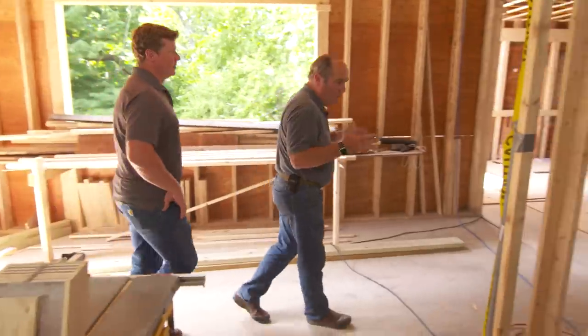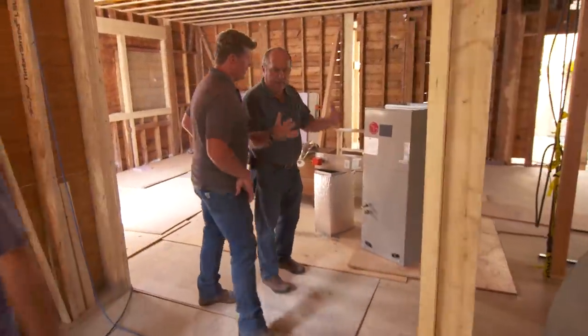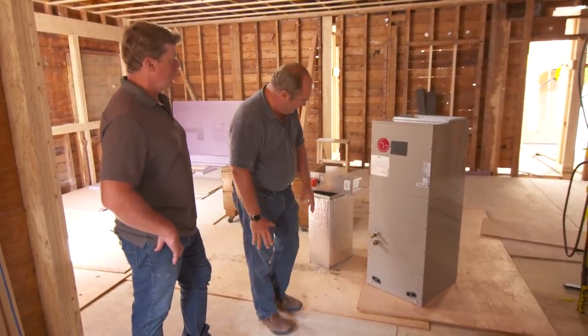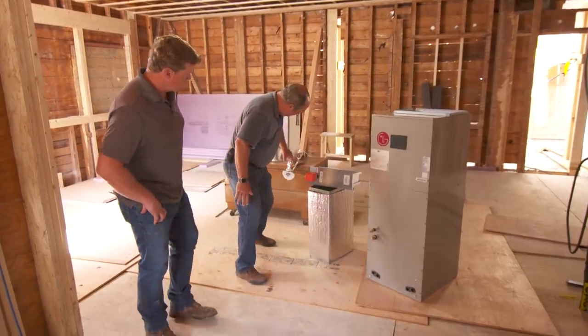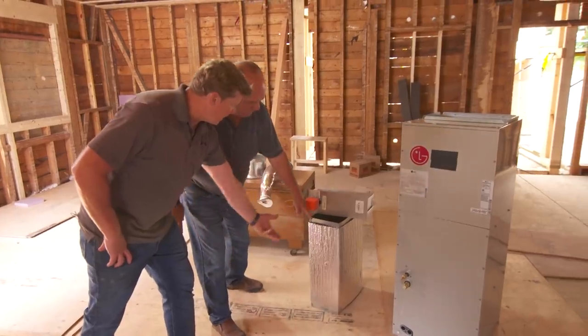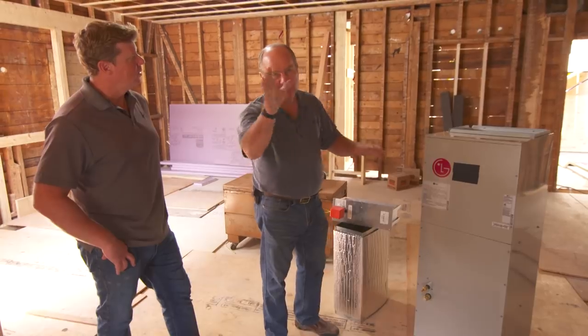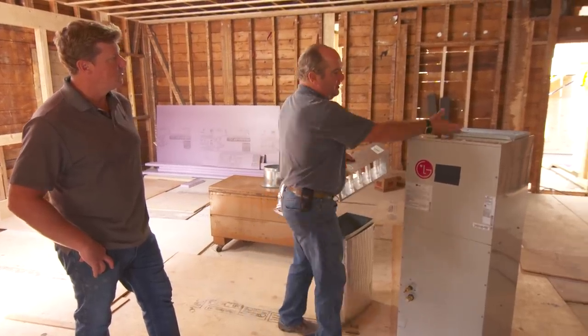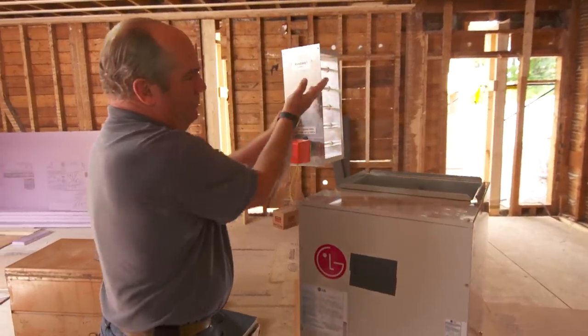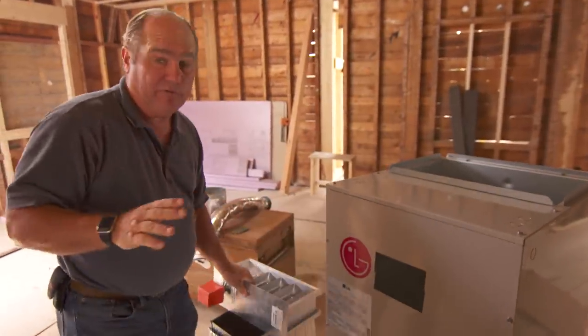Nice. All right. From a cooling standpoint, we're going to have a separate ducted cooling system. So the first floor is, again, wide open down below, so we can go conventional duct work. We don't have to go with our regular small duct that we often have to use. This goes into the basement and comes up through the first floor? That's right, through the first floor. We'll have an air handler, something like this, and I think we'll break this first floor up into two zones. So we'll come up with cool air into the duct work, and then there'll be a motorized damper on both sides so the air can go to one half of the building or to the other. So that's pretty straightforward on the first floor.